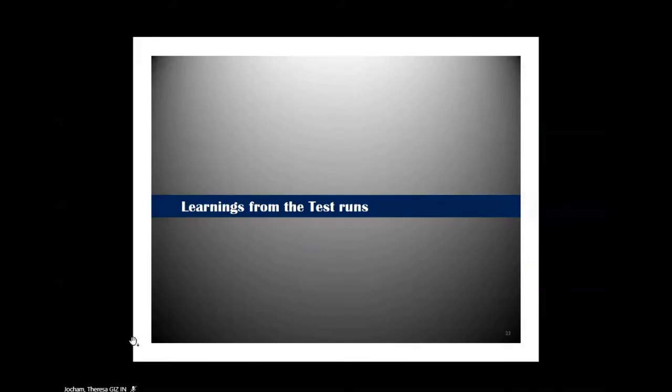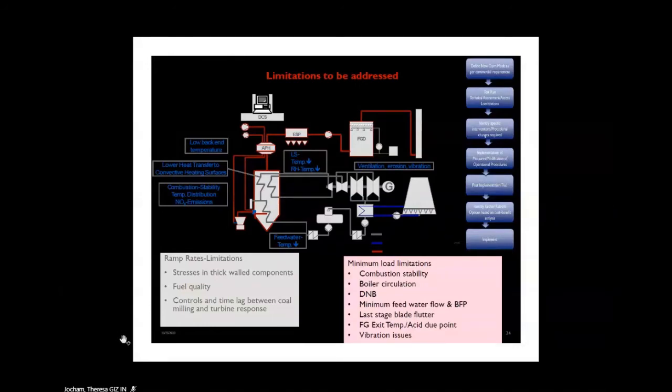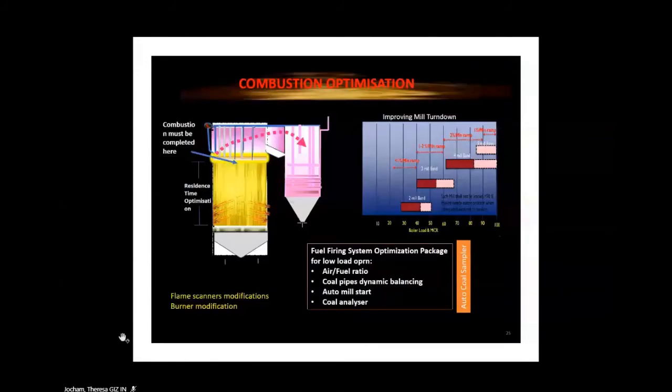Criteria was like base load, those units which don't have the coal. They just cannot run on flexible mode. These are the main areas where you find flexible operation problems. This is based on all the test runs. We have had around a number of tests, seven, eight test runs in many stations and two are ongoing. So these are some of the common findings. Combustion is very important, because turbine side, you have very few problems. Only you need to check your temperatures. And again, the vacuum, you need to maintain water chemistry side, but combustion optimization is the primary thing.